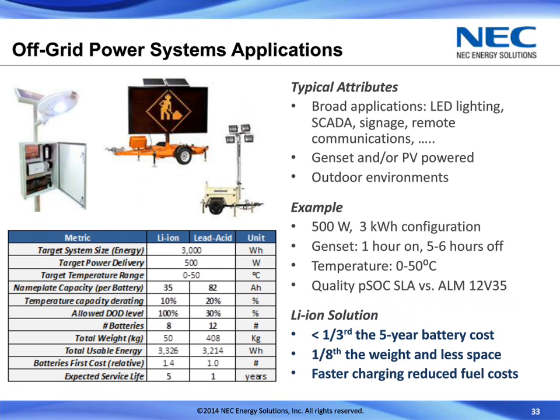Okay, so the last one, off-grid power systems. And there are broad applications really for this type of situation. You see lots of LED lighting, SCADA, signage, remote communications, etc. And a lot of these are PV powered, and some diesel gensets, most of them outdoor environments. For this example, we chose 500 watts, 3 kilowatt hour, so you have a 6-hour runtime. And again, wide temperature range, 0 to 50 degrees C.